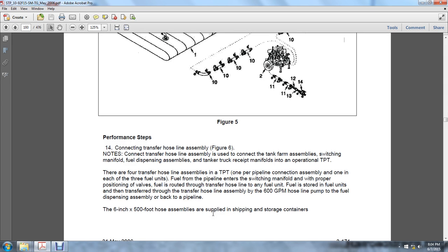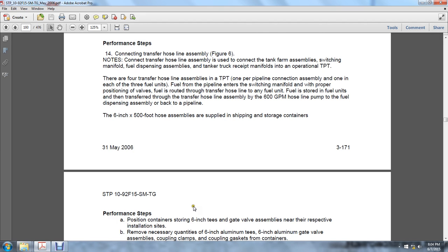1 in each of the 3 fuel units. Fuel from the pipeline enters the switching manifold with the valve in the proper position. Fuel is routed through the transfer hose line to any of the fuel units. The fuel is stored in the fuel units and transferred through the transfer hose line assembly. About 600 gallons per minute is pumped through the hose line into the fuel dispensing assembly and back into the pipeline. The 6-inch 500-foot hose assemblies are supplied in shipping and storage containers.